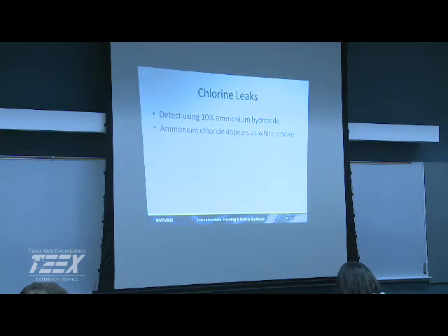If you are on gas, Jared mentioned earlier, how are you going to detect it besides your door handle falling off? You're going to go in there and use ammonium hydroxide. You're going to see your whiffs of smoke. You're going to be able to pinpoint your area and go in there and do a repair, if you're properly trained and you have the proper equipment.